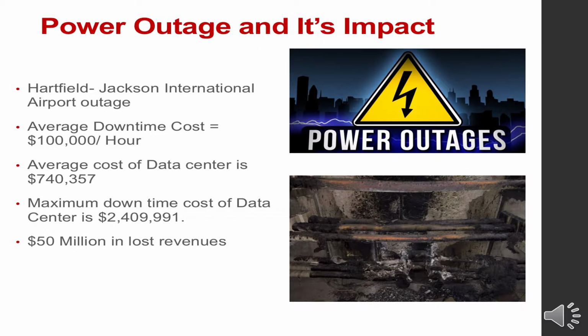So reports from the utility company which was serving the airport and the airport sources confirmed the fire's intensity damaged 2 substations serving the airport, including the airport's redundant system, which is supposed to provide the backup power. The root cause of the fire is supposed to be a piece of switchgear that was in the underground electrical facility, failed, and it started the fire, which quickly spread through the tunnel and damaged the entire power system.